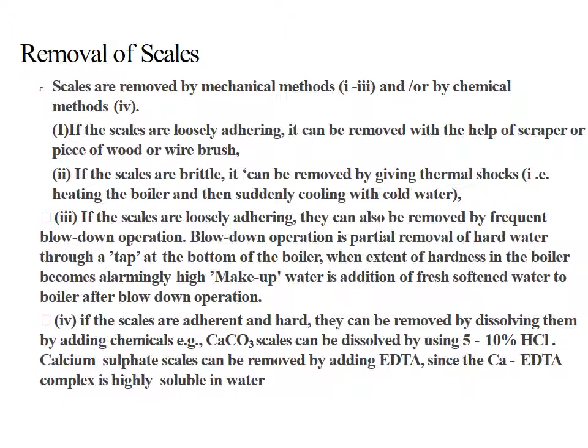If the scales are adherent and hard, they can be removed by dissolving them or by adding some chemicals, e.g. calcium carbonate scales can be dissolved by using 5 to 10% hydrochloric acid. Calcium sulfate scales can be removed by adding a solution of EDTA, ethylenediaminetetraacetic acid. Since the calcium EDTA complex is highly soluble in water, when a solution of EDTA is added to the boiler, the calcium sulfate scales deposited on the inner wall of the boiler get dissolved in the solution by forming a calcium EDTA complex. Calcium EDTA complex is water soluble and can be removed easily. In this way, the scales deposited on the inner side of the boiler are removed.